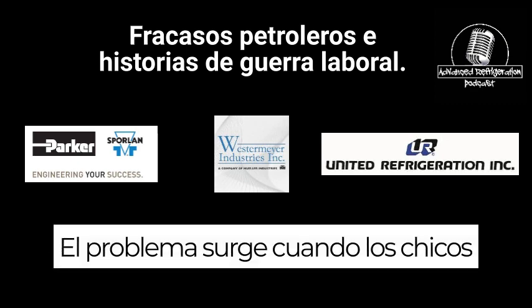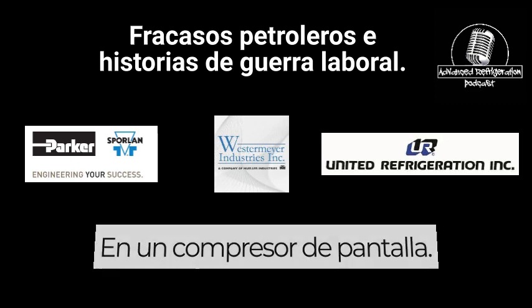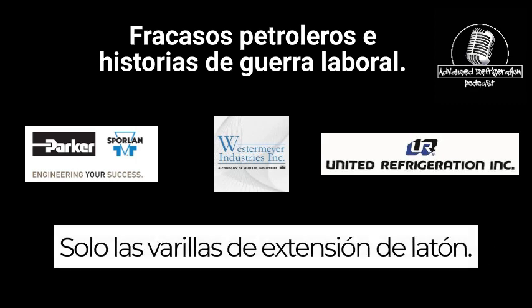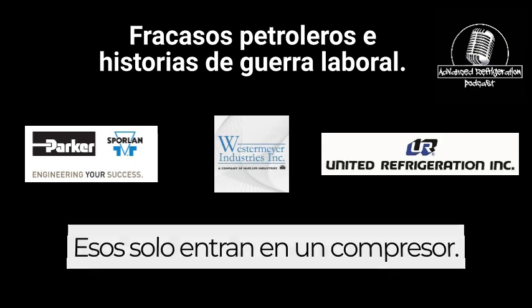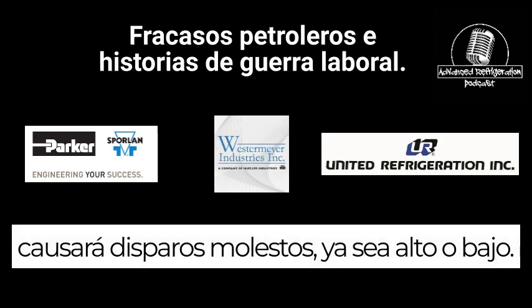The issue comes in when guys do not stick the rods in them in a scroll compressor. You do not need the rods in a recip compressor, only the brass extension rods. Those only go in a scroll compressor. And if you do not have them in there, they will cause nuisance trips, whether it be high or low.